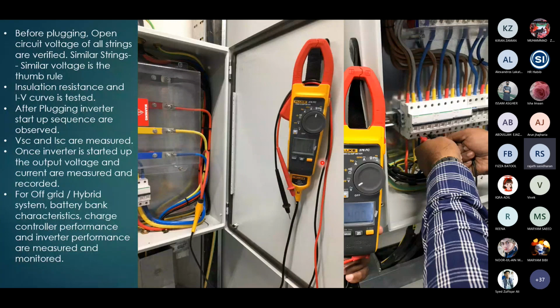In the PV system, we check the voltages. If the voltages are fine, we compare with the different strings. Say if you have 10 strings and I'm getting almost similar voltage for 9 strings, and one is giving me, say, 70% less, that means there is something wrong in that string. So we can go and check that string before we plug it into the inverter. We also do something called IV curve. It's a huge topic. Please read up on it.